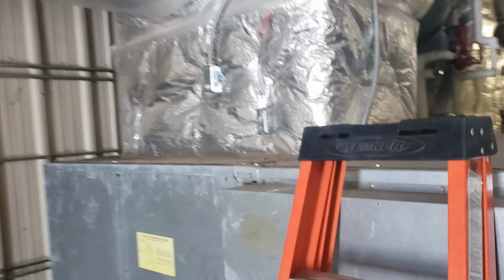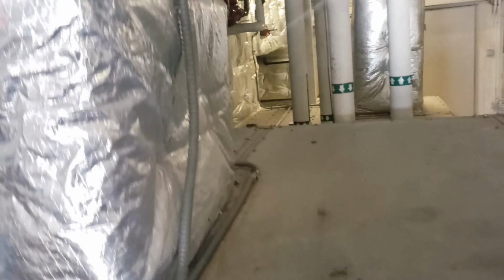So anyway, it was calling for it through the EMS. It just wasn't running, since we're in auto. Now what I need to do is verify that when the fire trips, it's actually going to shut the air handler down so they can get their commissioning test. You can see our duct detector up here.